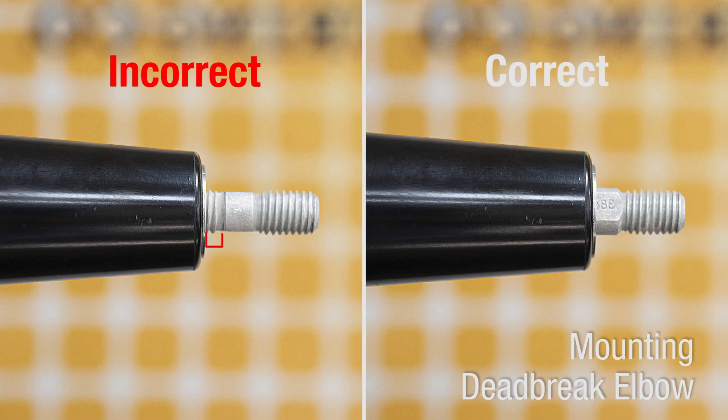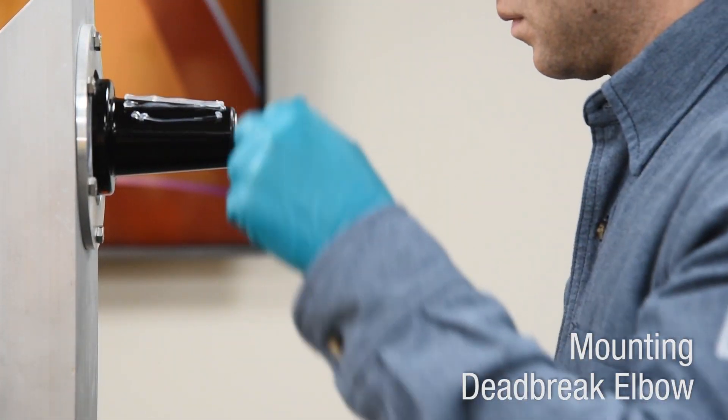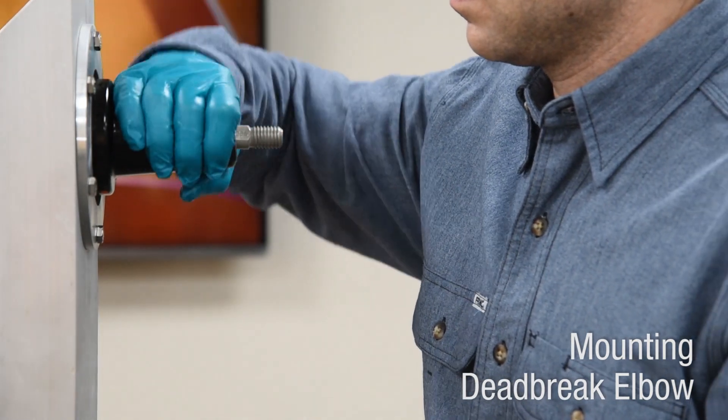If any threads are visible, confirm the correct stud is being used and confirm the bushing and stud are not damaged or cross threaded. Using supplied or approved silicone grease, clean and lubricate the deadbreak interface and bushing.